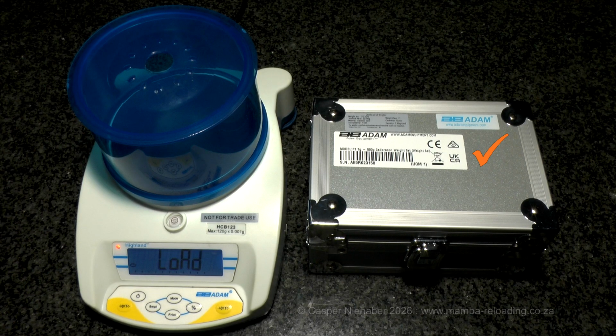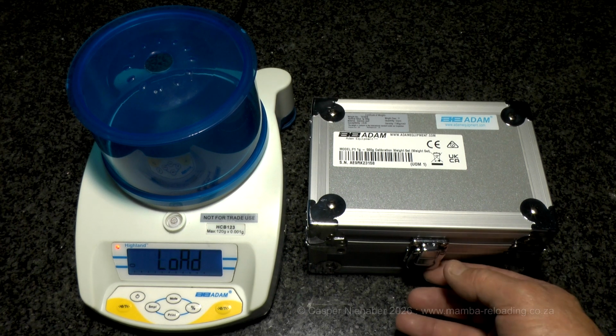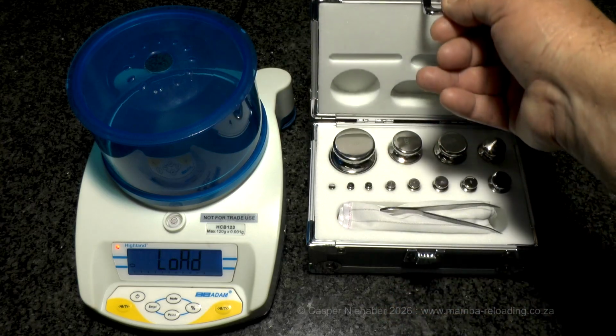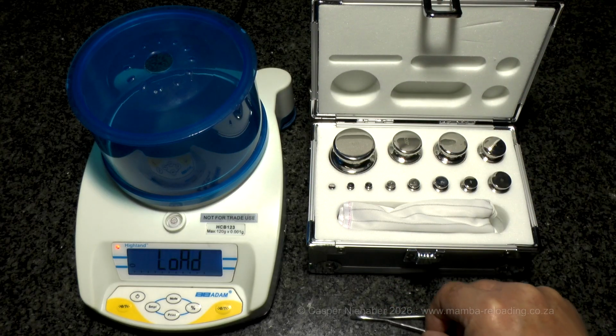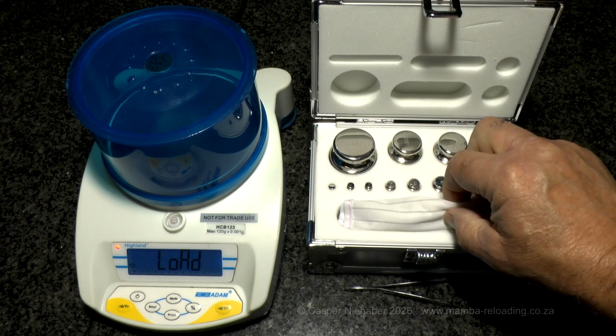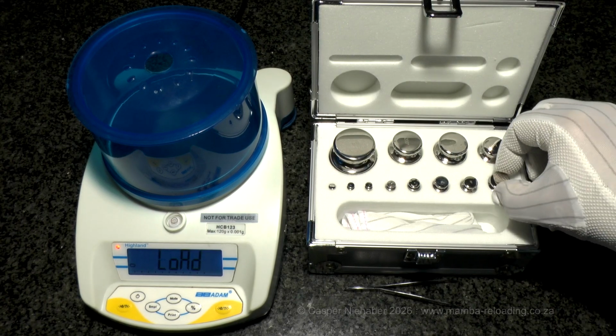Please note, using proper, well-made test weights, precisely manufactured to a specific mass, is critical when calibrating a precision balance. Calibration is only as accurate as the reference mass used. An inaccurate weight inevitably results in an inaccurate calibration. Open the Adam F1 weight set and put on the white glove. Remove the 50 gram test weight.